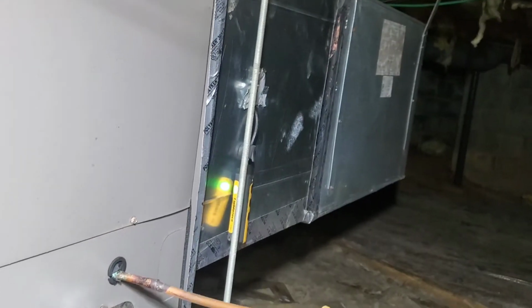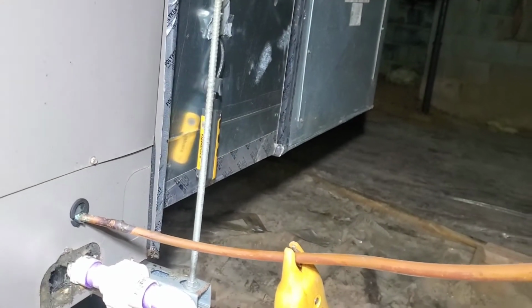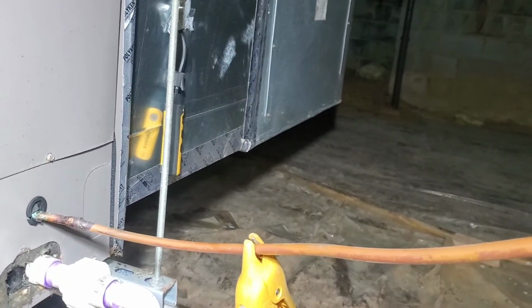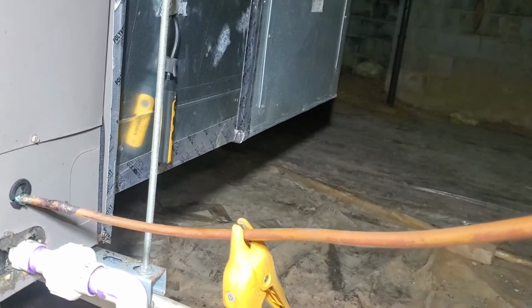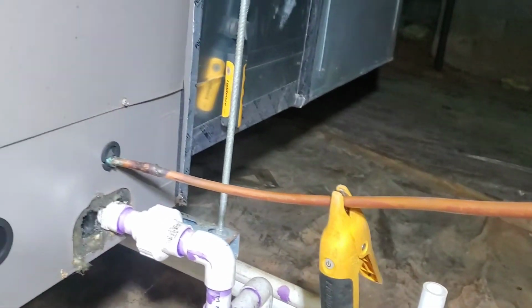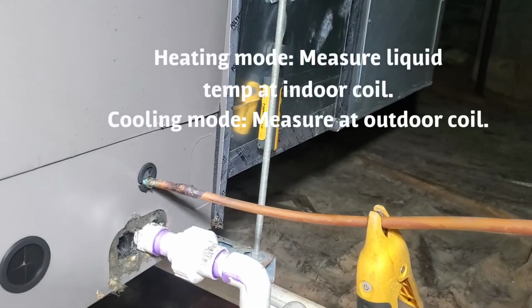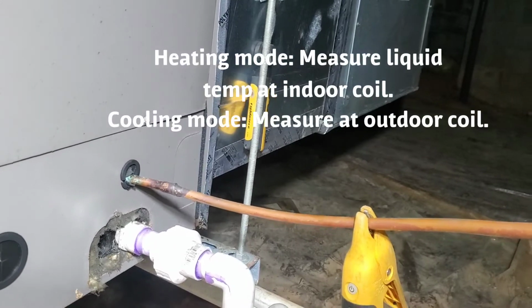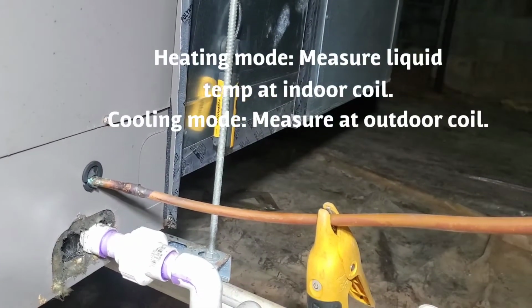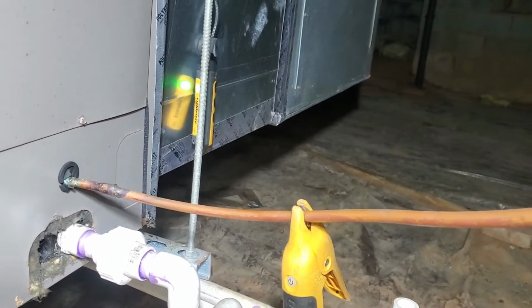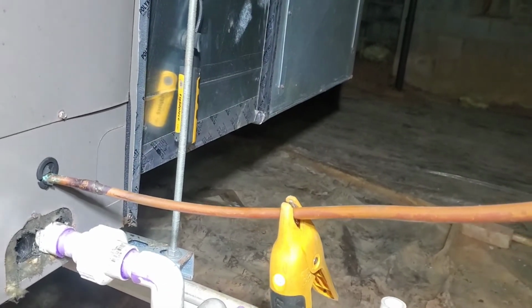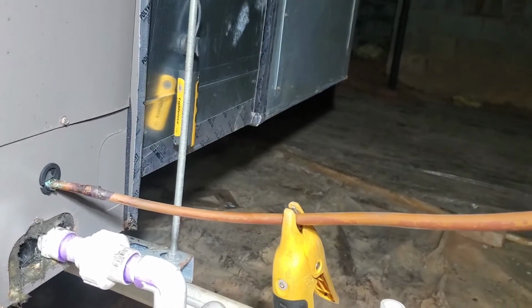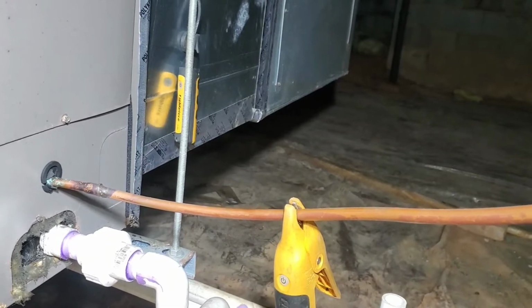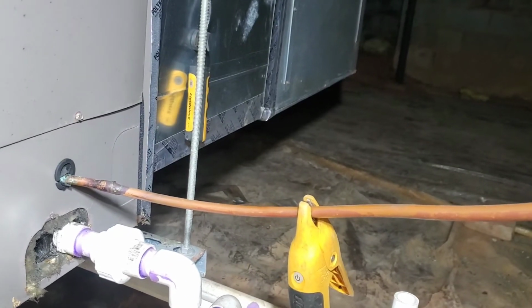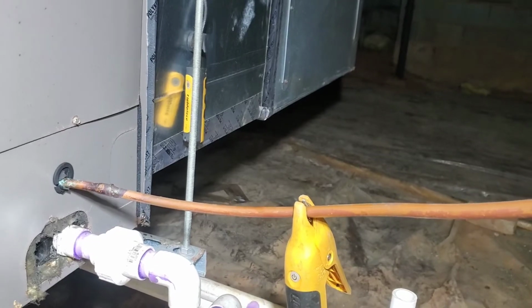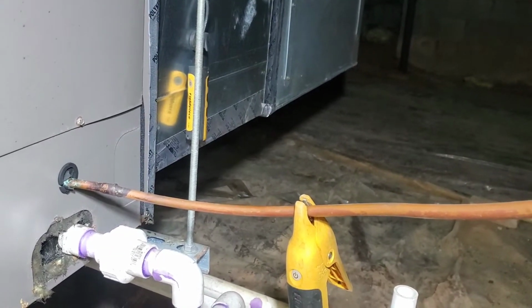The other thing I want to point out is sensor placement. Make sure when you're measuring approach temperature in heating mode that your liquid line temperature is being sensed when it comes out of the indoor coil. That's because if you've got a long line set that goes through an unconditioned space, that liquid will start losing temperature because it's cold in the surrounding area around it. And so if you're measuring it at the outdoor unit, you're going to be a few degrees off, and just a few degrees could be the difference between you thinking a unit is undercharged or properly charged.